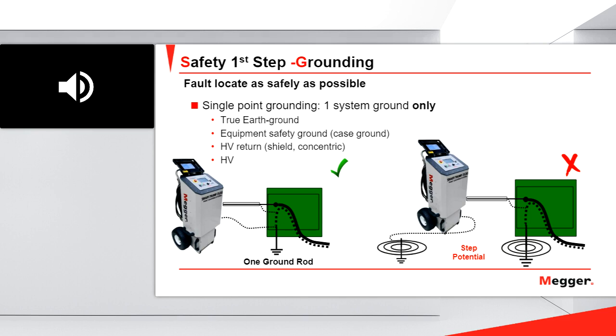If you see the picture on the left, you will see that I have my thumper, my fault locator here, and I connect first the safety ground to this ground rod. Then I connect the high voltage cable of my thumper to the conductor of the faulted cable, and the other connection is to the metallic shield or the neutral of my faulted cable. Okay, and if you see in this picture, all the neutral and ground connections are on the same rod, exactly the same ground. This is what we call single point grounding. Single point grounding. Okay, this is very important for safety in fault location.